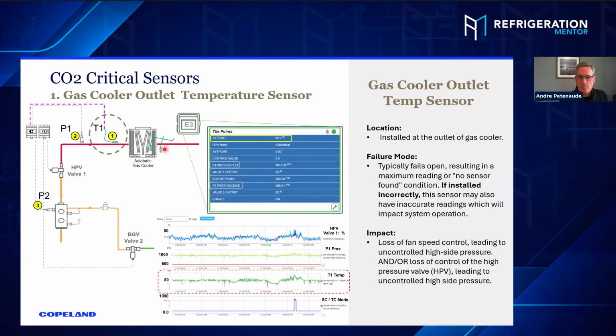So in this particular case, it's measuring only about 84 degrees. So it's only 2 degrees subcooling, right? Which is equivalent to about 1,012 pounds of pressure. So the information's there. This is what you've got to watch, and this is the graphing. We've done a few sessions before on the high pressure valve. You've got to go in and graph this stuff and look at it.